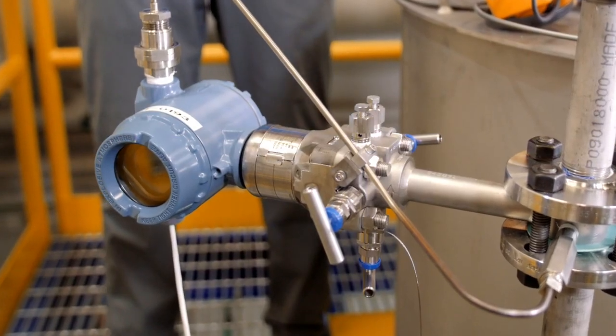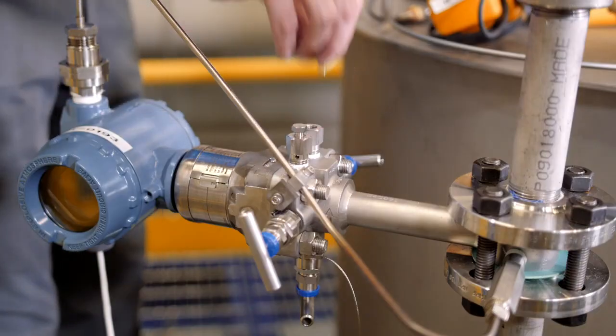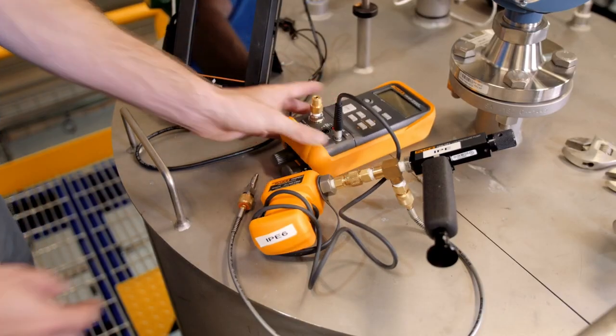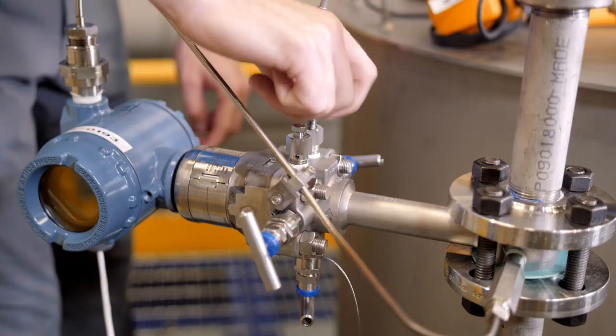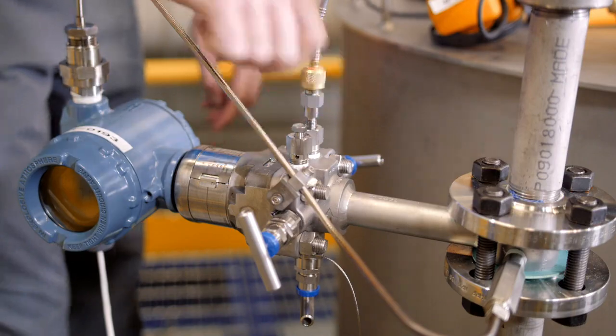We'll start by calibrating the differential pressure sensor, also known as a DP sensor. It's important that the DP sensor be calibrated at line pressure to negate any line pressure effects. The first step will be to connect a pressure source that is at least 3 times as accurate as the transmitter. Next, we will connect the Emerson Trex.